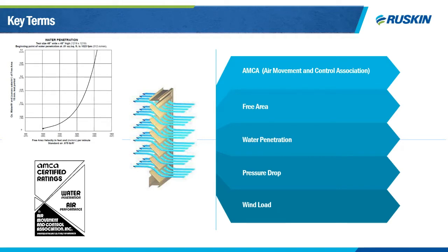And finally, there's wind load, which is probably one of the most important aspects to consider when looking at a louver. Wind load refers to any pressures or forces that wind exerts on a building or structure. Different areas will have different design wind load requirements depending on the basic wind speed of the area and the size and shape of the building. Ruskin's standard wind load is 20 pounds per square foot, but we can build to any requirement and provide additional support to the louver to ensure it meets those requirements.